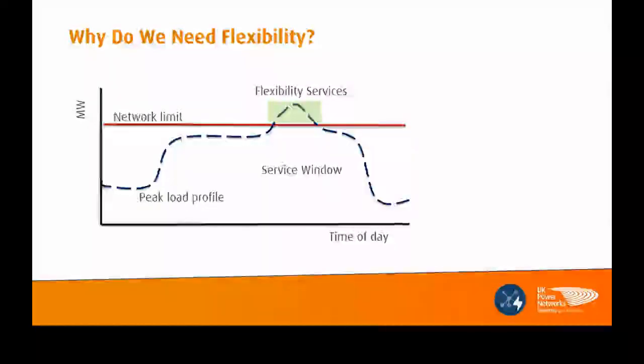When peak demand starts to reach or exceed the limitation of the network, traditionally we would go out and reinforce the network, which could mean uprating cables or replacing transformers. But an alternative is to contract with flexibility services, a resource that can reduce demand on the network at particular times of day, thereby avoiding or deferring that reinforcement.